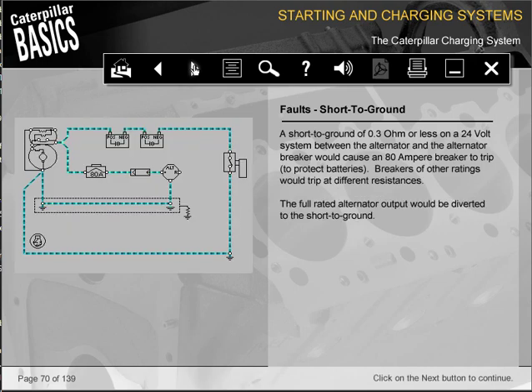A short to ground of 0.3 ohm or less on a 24-volt system between the alternator and the alternator breaker would cause an 80 ampere breaker to trip to protect batteries. Breakers of other ratings would trip at different resistances. The full rated alternator output would be diverted to the short to ground.